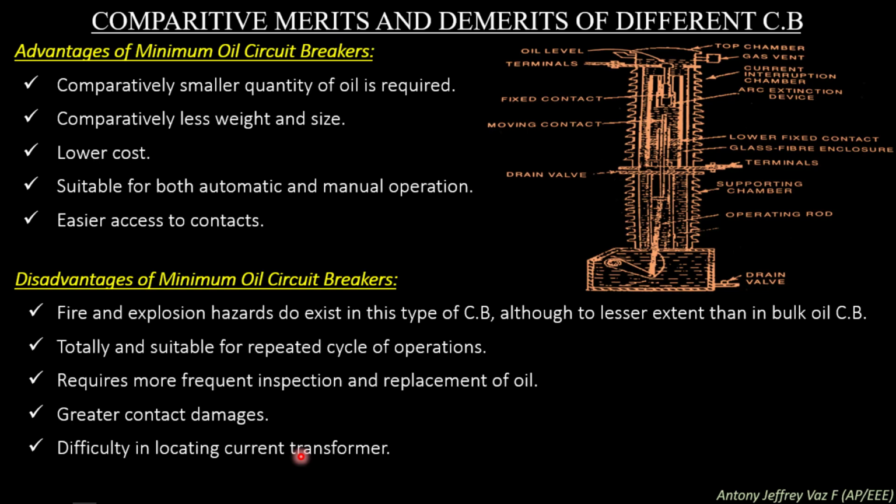Difficulty in locating current transformer. In bulk oil circuit breakers, the current transformers can be located at the top of the porcelain bushings. Here in the minimum oil circuit breaker, there is no possibility of constructing or inserting a current transformer in this type of minimum oil circuit breaker design.